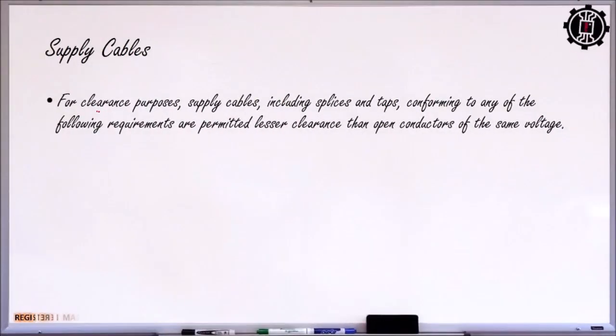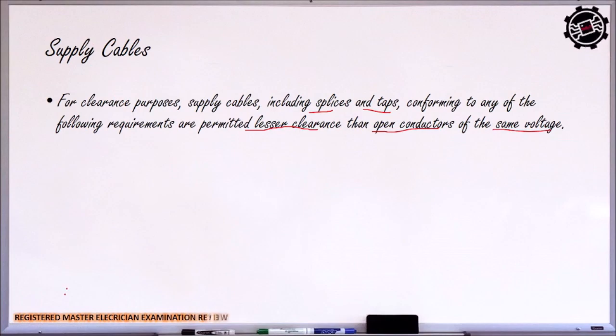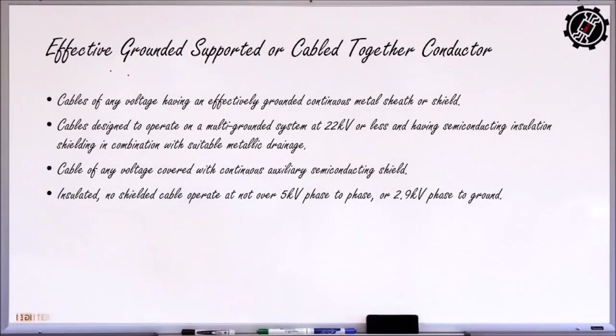So supply cables. So for clearance purposes, supply cables including splices and taps conforming to any of the following requirements are permitted to have lesser clearance than open conductors of the same voltage. So, ano yung mga conditions, no, in order for our supply cables to have mas mababa na clearance? So the first is the effectively grounded, supported, or cabled together conductor. So yung nakabundle na conductor which are effectively grounded. So cables of any voltage having an effectively grounded continuous metal sheath or shield. Cables designed to operate on a multi-grounded system at 22 kilovolts or less and having a semiconducting insulation shielding.